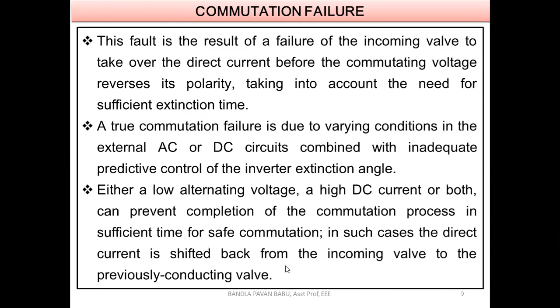Next, in such cases the direct current is shifted back from the incoming valve to the previously conducting valve. Here we have full control over this inverter station, because we are applying forced commutation, so we can easily send it back. Each switch can be controlled, because the input is DC. It is not similar to the rectifier station, where alternating pulses are generated continuously and a lot of stresses will be there. Coming to the inverter station, the input is DC, so the severity will be somewhat less. If this type of failure, the commutation failure, comes, there are more chances to eliminate it easily.